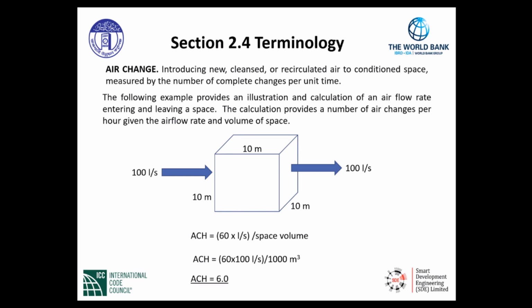The following example provides an illustration and calculation of an airflow rate entering and leaving a space. The calculation provides a number of air changes per hour, given the airflow rate and volume of space. As seen, we have a volume of space that essentially measures 1,000 cubic meters. We have an airflow rate entering at 100 liters per second and an airflow rate leaving at 100 liters per second. The air leaving would be, in fact, the exhausted air, while the entering air is new air, completely cleansed or recirculated to the conditioned space.